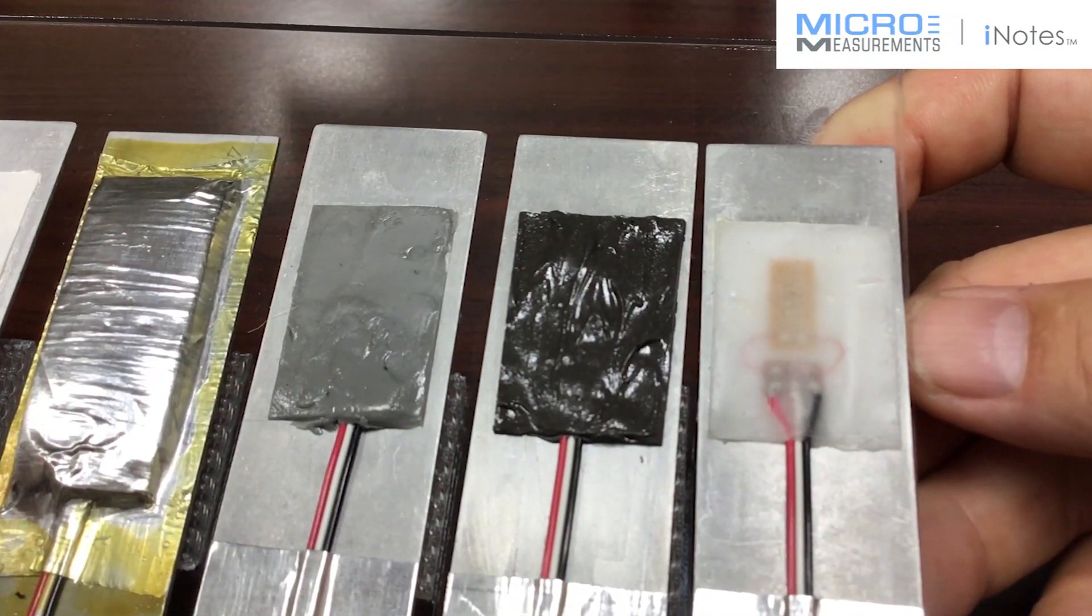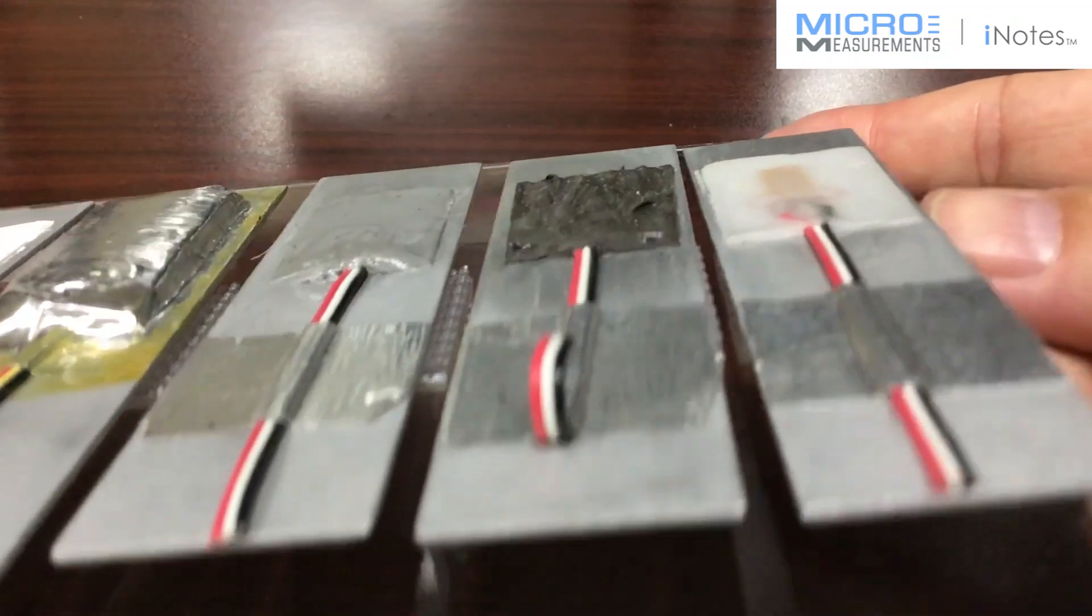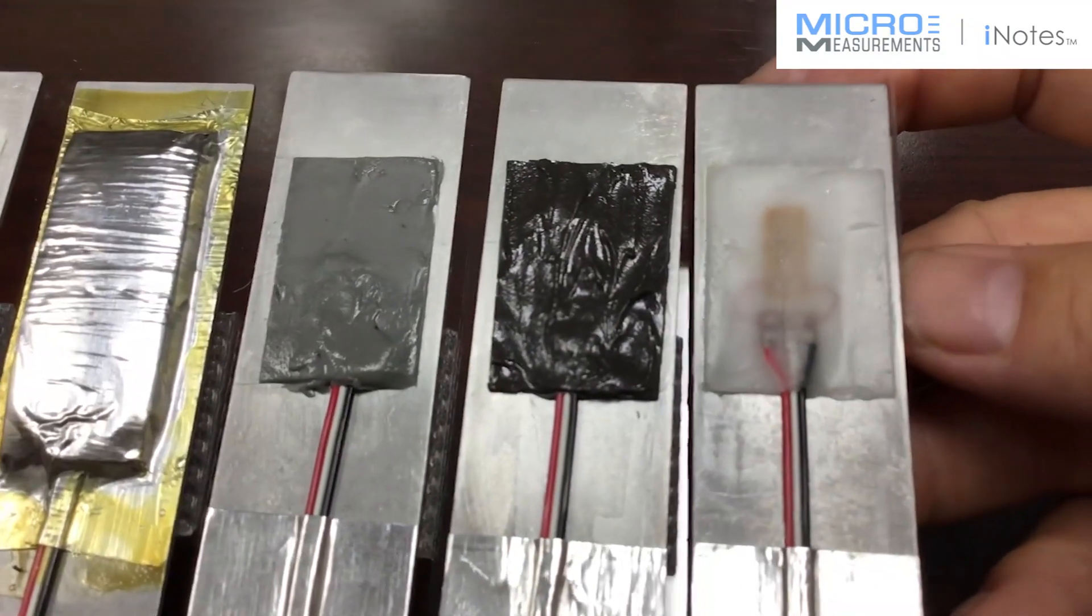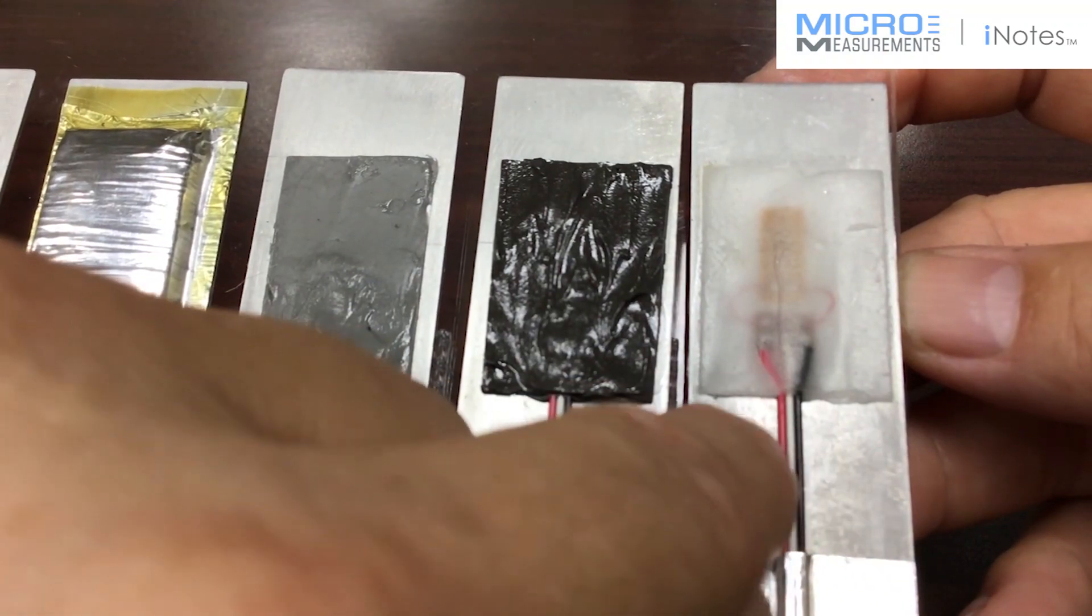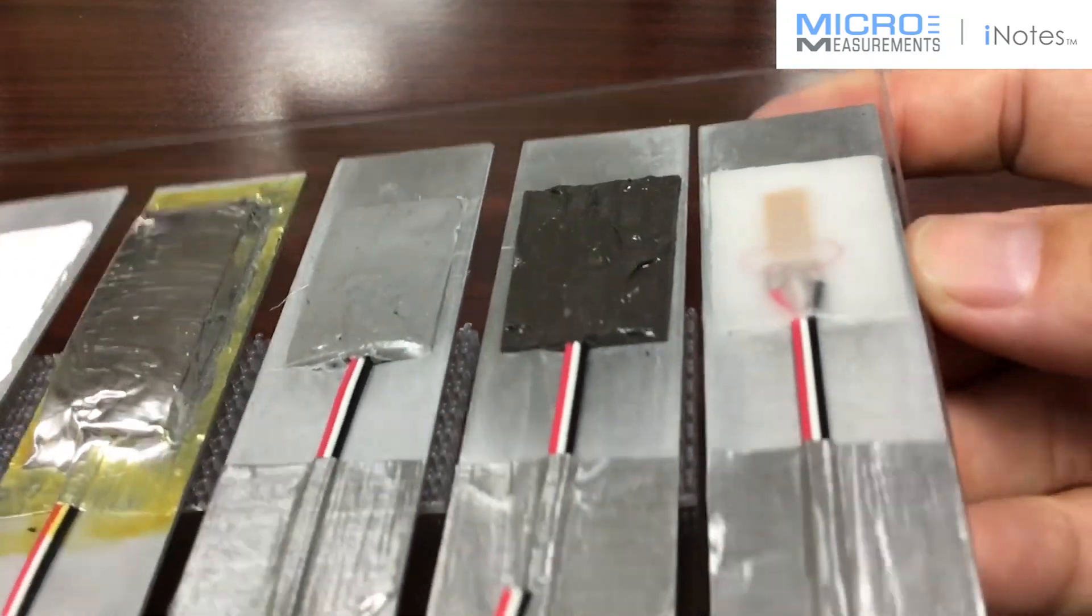This wax as I mentioned is a great moisture barrier but it's not very good mechanically. So a lot of times you do have to put something else over top of it to add additional protection. And also if you look at this one you'll notice how smooth it is on the surface. If you're ever putting wax on over top of strain gauges, you want to make sure you warm the surface of the part before you brush the wax on and that'll help it wet and look nice and smooth like that.